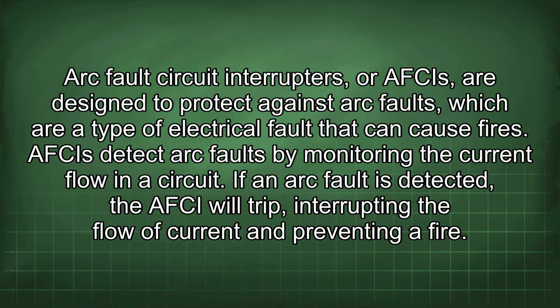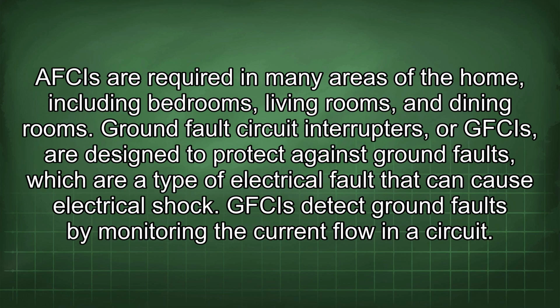Arc fault circuit interrupters, or AFCIs, are designed to protect against arc faults, which are a type of electrical fault that can cause fires. AFCIs detect arc faults by monitoring the current flow in a circuit. If an arc fault is detected, the AFCI will trip, interrupting the flow of current and preventing a fire. AFCIs are required in many areas of the home, including bedrooms, living rooms, and dining rooms.